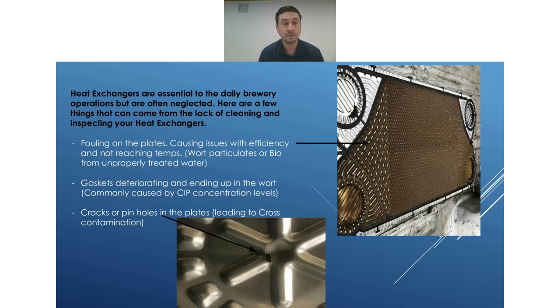These may come from just a lack of cleaning or inspecting your heat exchanger. One major one is fouling on the plates. This can come from water—if you're using a well and there's a lot of calcium or minerals in the water, you can get what's called scaling on your plates. What this will do is cause a negative effect on your heat transfer rate, so you're not going to be as efficient.